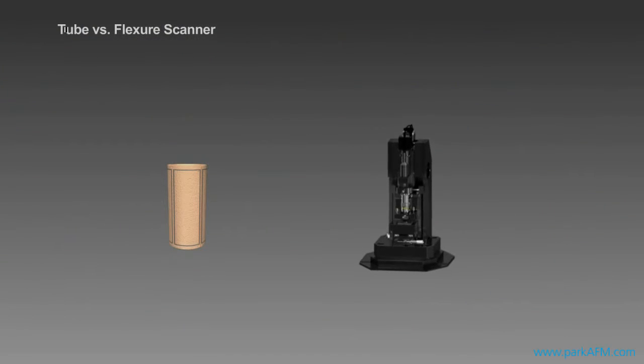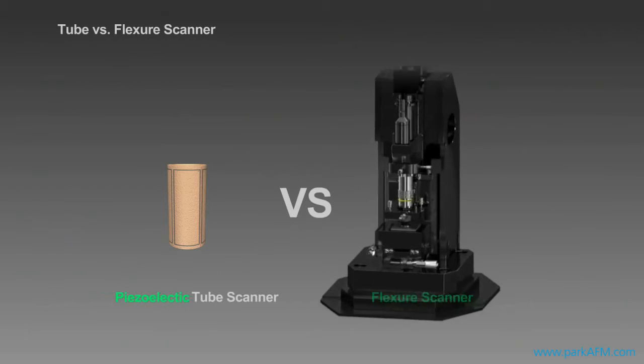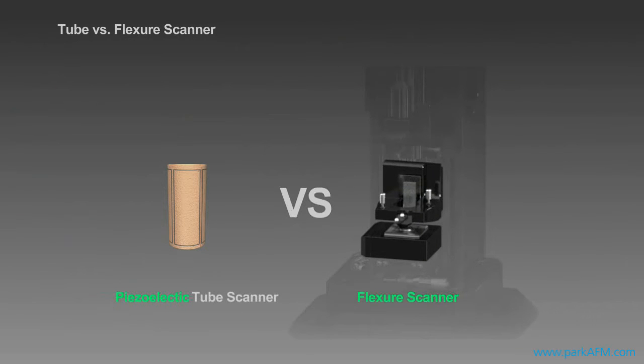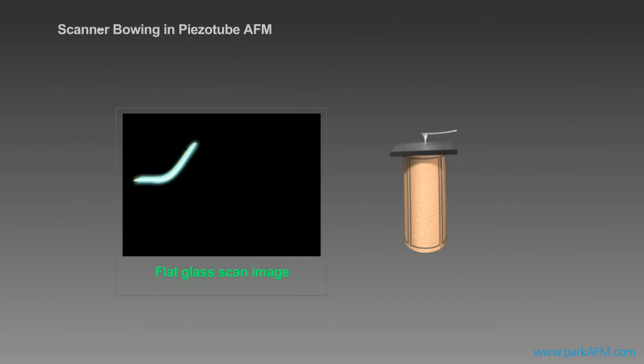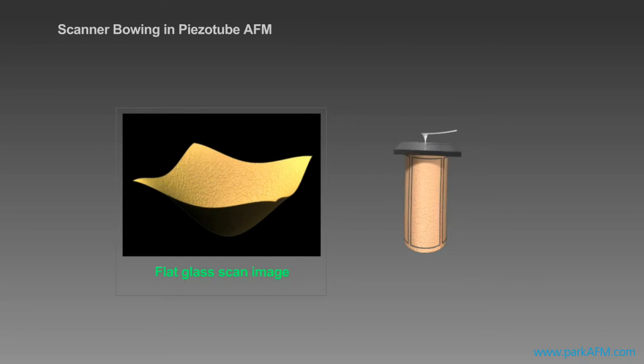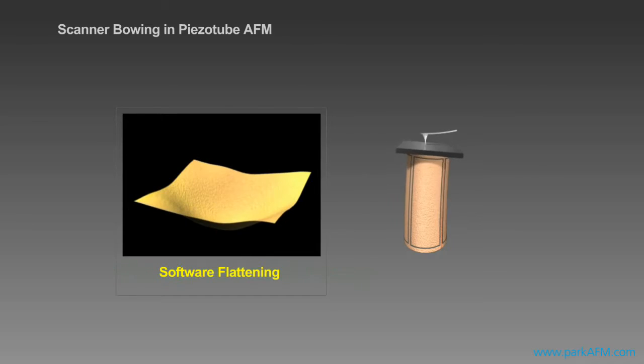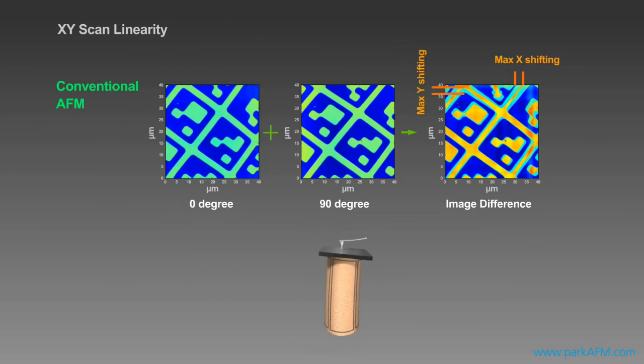Park Systems has changed the basic AFM in different ways to grow its power and make it more useful than ever before. The basic AFM uses a tube scanner to change the relative positions of the probe and sample. A tube curvature changes the XYZ axes. This can distort images and make it very hard to get correct measurements.